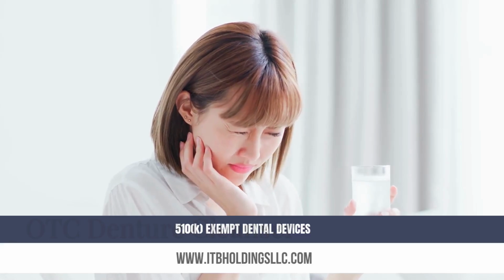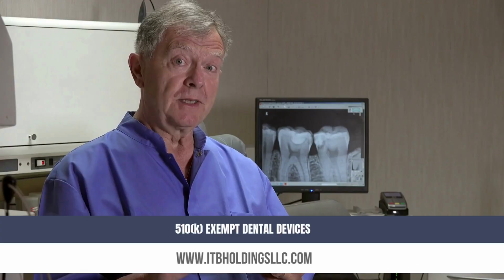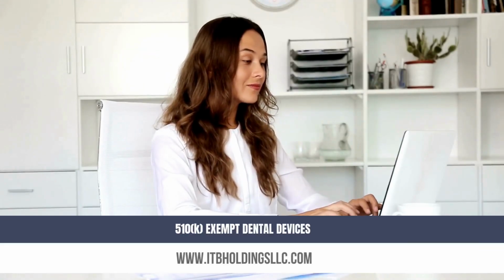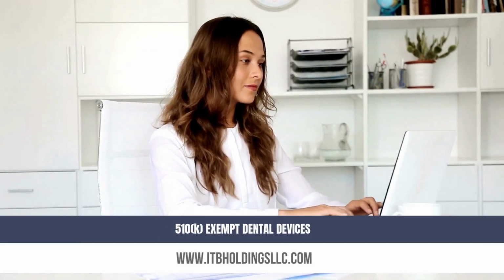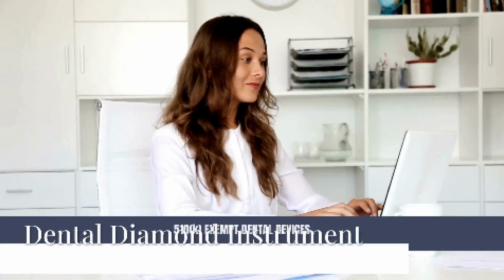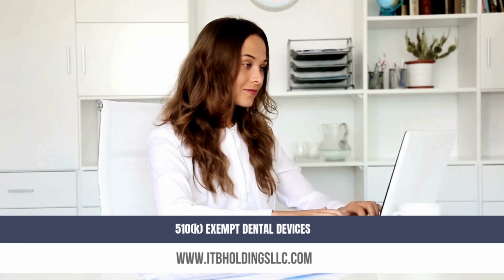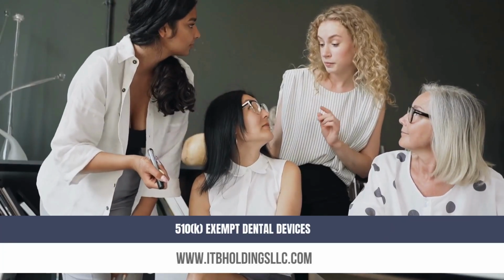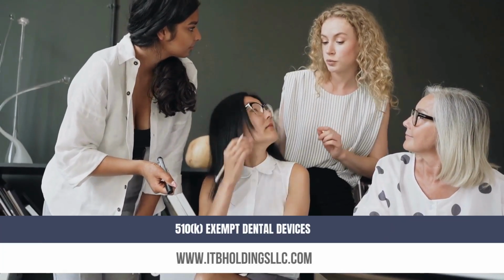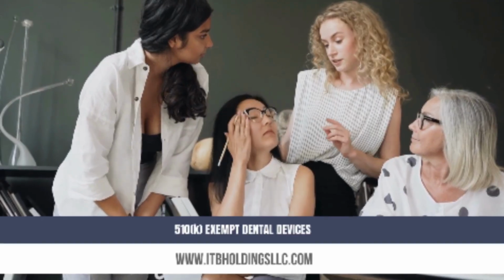OTC denture cleanser. Prescription denture cleanser, product code NUX, requires 510(k) clearance. An Rx denture cleanser is an effervescent tablet for the removal of microorganisms from removable dentures and retainers. Over-the-counter denture cleanser, product code EFT, is 510(k) exempt. Dental diamond instrument. Reprocessed diamond dental instrument, product code NLD, requires 510(k) clearance. Diamond dental instrument, product code DZP, is 510(k) exempt.